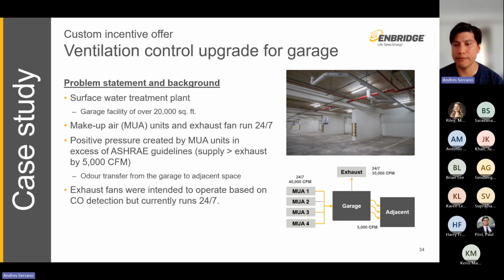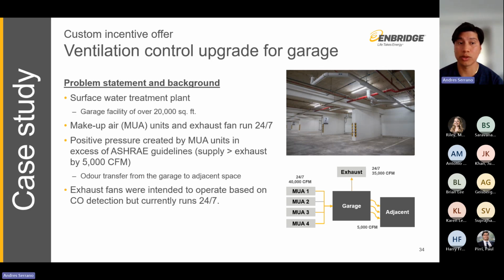The next case study is a ventilation control upgrade for a garage. This one's a little bit more nuanced, but I will try my best to explain what exactly is going on here. This was at a surface water treatment plant that had a garage of over 20,000 square feet. The makeup air units and exhaust fans were running 24/7. We also saw an imbalance of air between the supply and the exhaust. Essentially, the makeup air was providing 40,000 CFM, while the exhaust was exhausting 35,000 CFM. This also led to an odor transfer from the garage to the adjacent space because of the imbalance of exhaust and supply air.